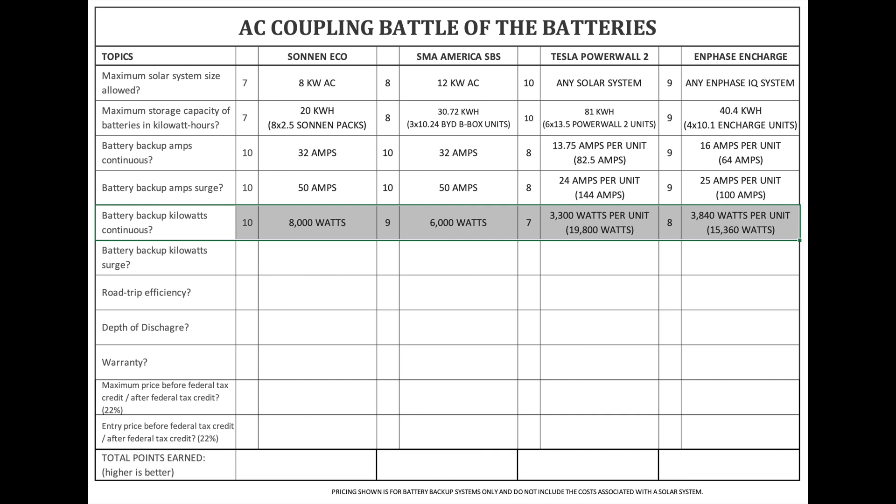Battery backup kilowatts continuous. Much like amps, kilowatt output of the system during a power outage is crucial — this is the energy the system can actually provide your home or backup panel. Just remember: amps start the devices and watts or kilowatts provide the power for them to run. The Sonnen Eco is 8,000 watts or 8 kilowatts. SMA America SBS is 6,000 watts or 6 kilowatts. Tesla Powerwall 2 is 3,300 watts or 3.3 kilowatts per unit, up to six Powerwalls for 19,800 watts or 19.8 kilowatts. Enphase Encharge 10 is 3,840 watts or 3.84 kilowatts per unit, up to four connected together for 15,360 watts or 15.36 kilowatts.